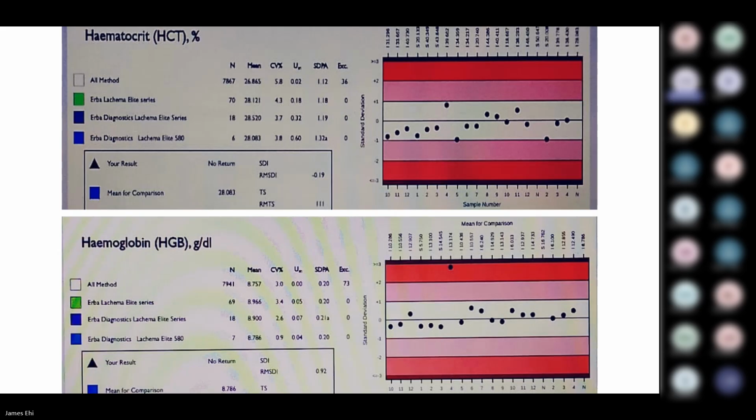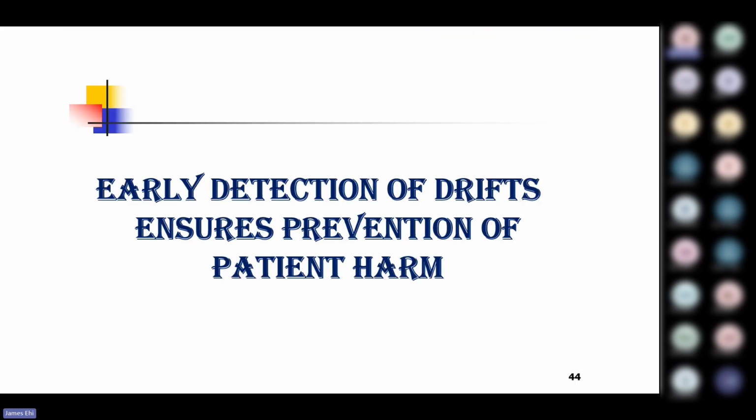Then the next question is: what if you have 10x within 1 SD? Is that okay? As I said, it's okay, most especially if it was not there when you started using the method in your lab, when you implemented the machine. But if everything is within 1 SD, let me, I think we had one very good example in these graphs here.